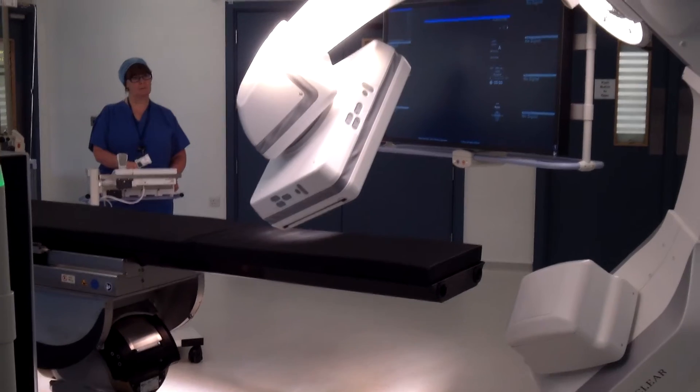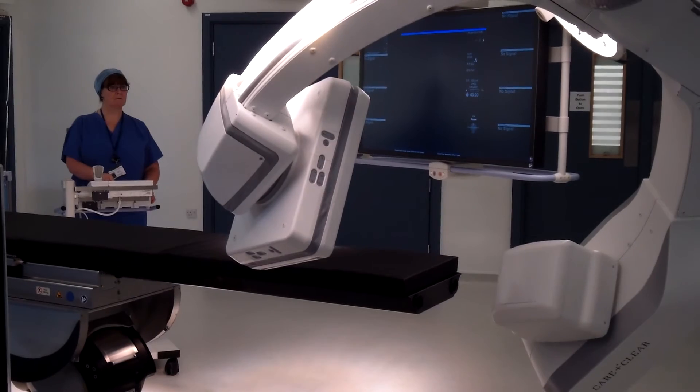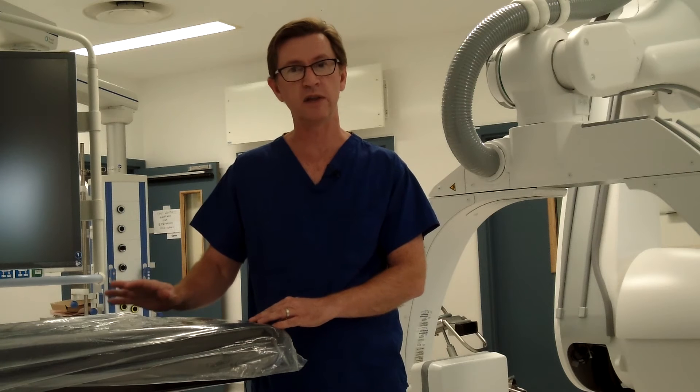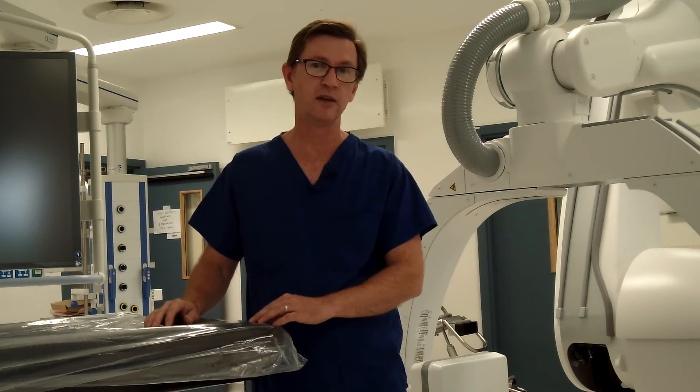Another advantage is that the table and the Artis Zeego are hard-wired together, so that any movements of one part of the table or the C-arm are mirrored in the other. This means that an operator moving the table will not have to independently move or adjust the C-arm to maintain the image position or character.